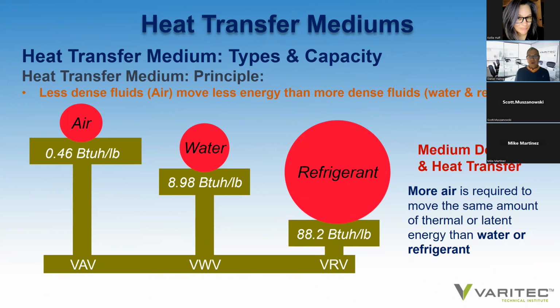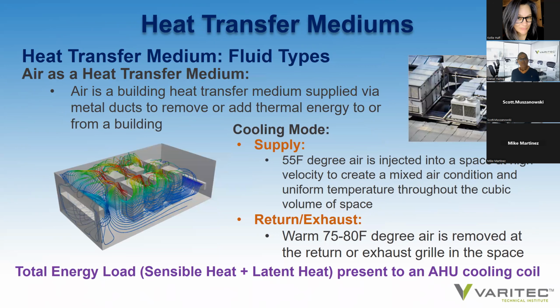Well, let's look at refrigerant. Refrigerant is even more dense than water and can hold 88.2 BTUs per pound of refrigerant. And refrigerant is a good example of why VRV systems, or variable refrigerant systems, are efficient, effective heat transfer mediums, because they can move so much energy with so little refrigerant. Consequently, these systems, if you bring that refrigerant local to each zone to condition each zone, are much more efficient in moving building energy from inside a building to outdoors, as well as for adding heat energy in heating mode. So air is a heat transfer medium. Let's look at air, our conventional mode of heat transfer.